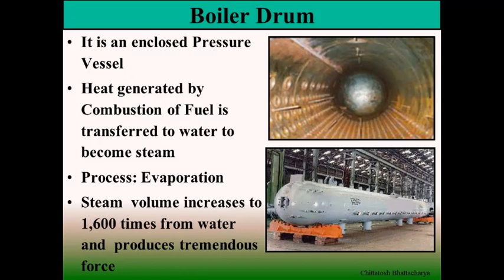So naturally, though it is placed outside the heat transfer zone and there is no heat addition, and two-phase existence of fluid is there, working fluid is there, this is important for wetting of the water walls as well as for continuous supply of saturated dry steam to the superheaters so that they do not get starved of the cooling medium, steam.